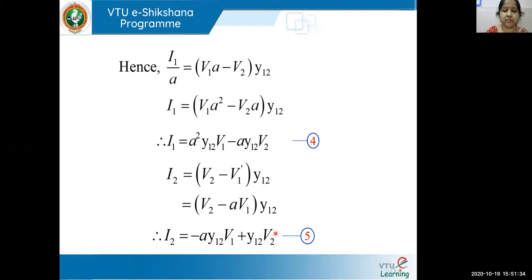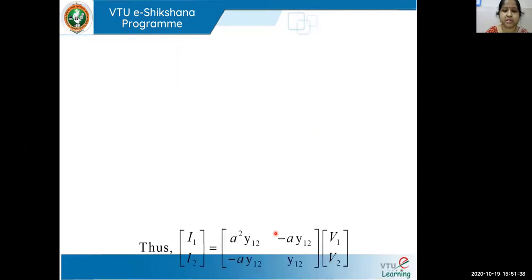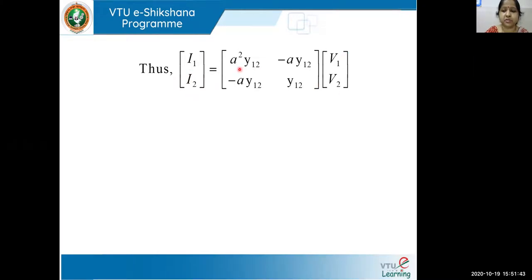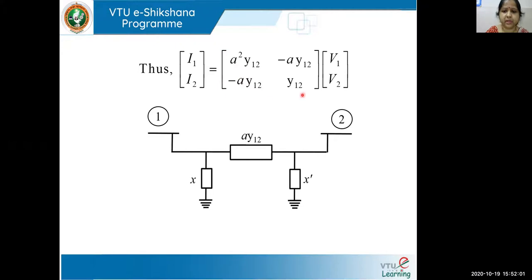Writing equations 4 and 5 in matrix form gives the YBUS. The diagonal elements Y11 = a²·y12 and Y22 = y12; off-diagonal elements Y12 = Y21 = −a·y12. The off-diagonal elements represent the negative of the series admittance, so in the pi model the series branch is a·y12. The diagonal elements usually include the half-line charging admittance — represented as x and x dash — whose values we need to determine.